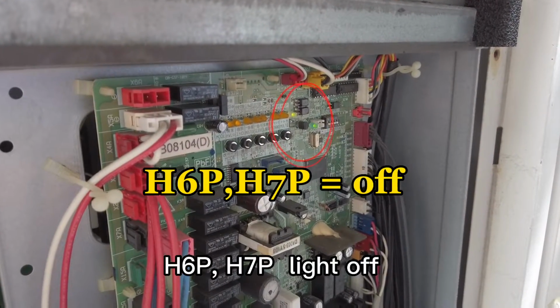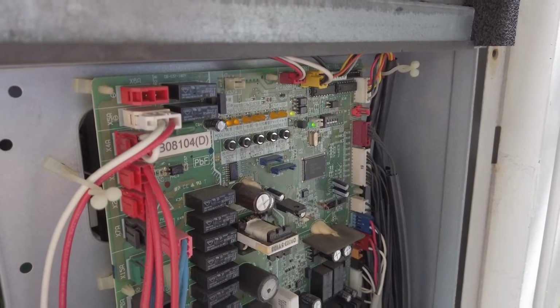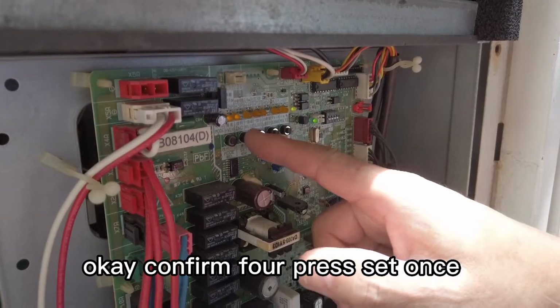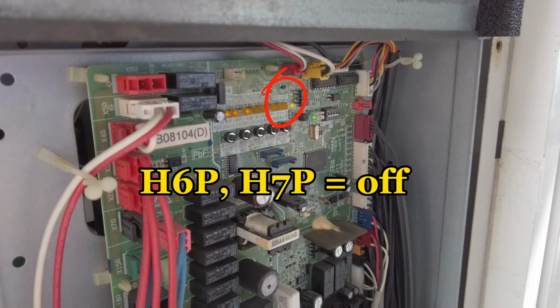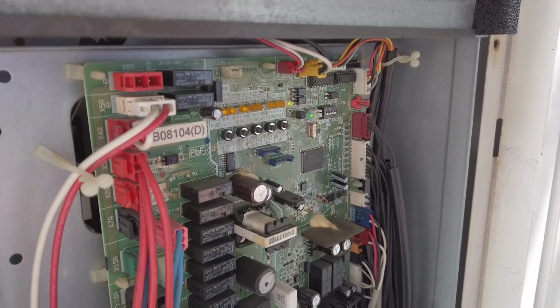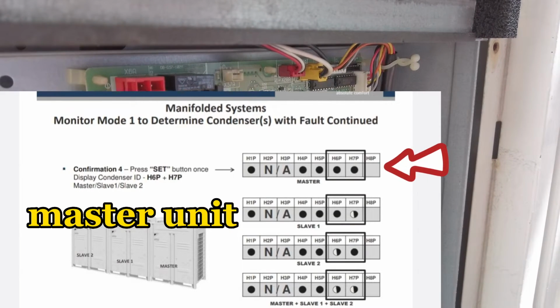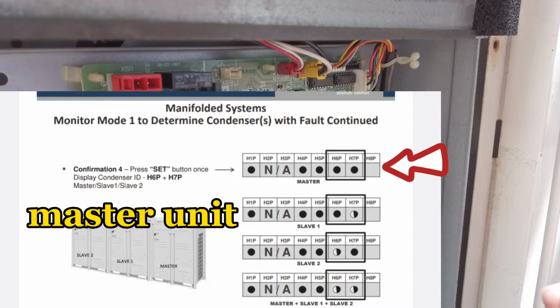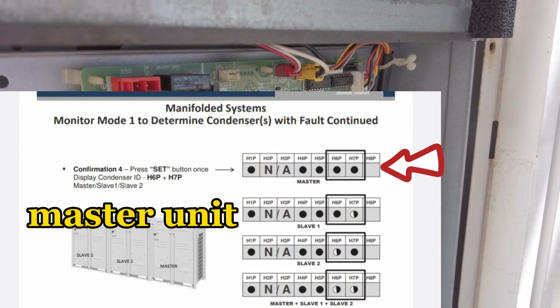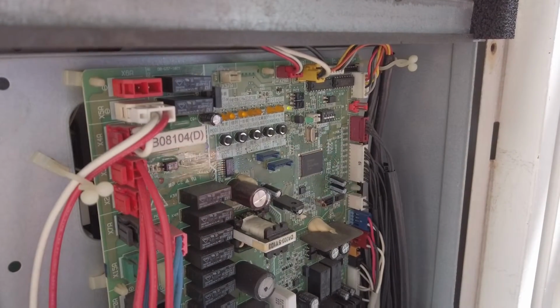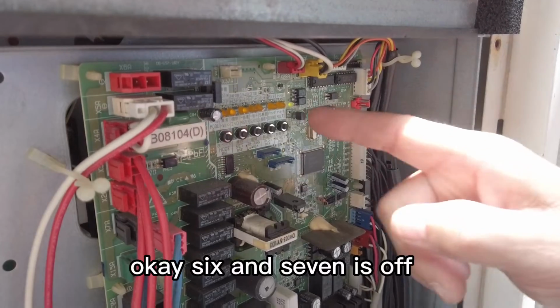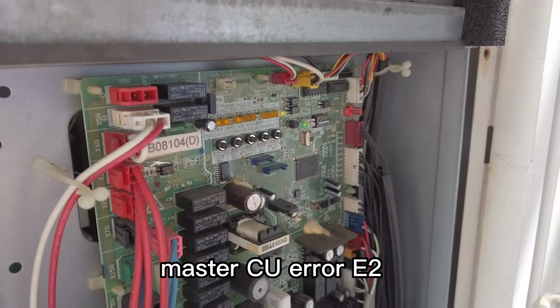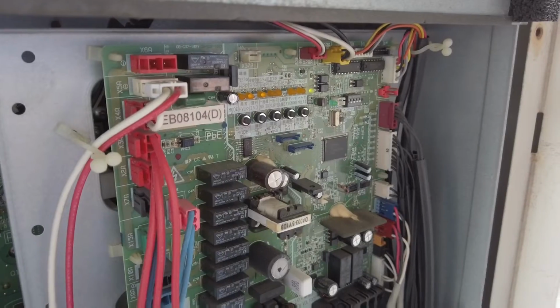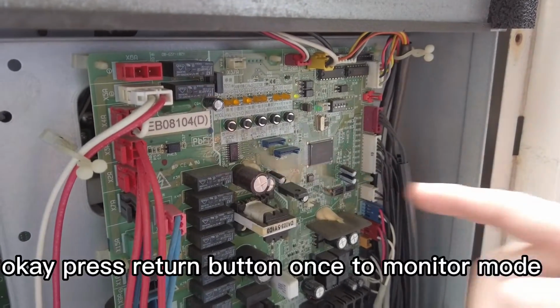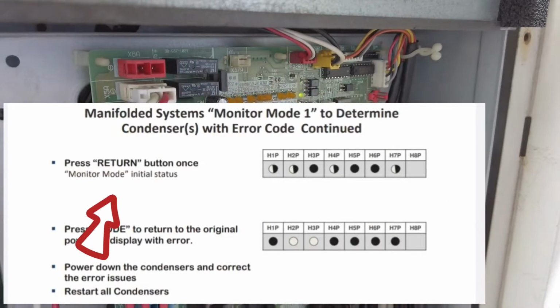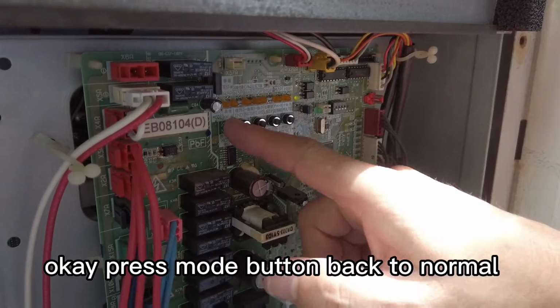Okay, confirm 3. Press set button once. Okay, LED 1 is blinking. LED 2 is on. Okay, confirm 4. Press set once. Okay, LED 1 blinking, LED 2, LED 3 is on. Okay, 6 and 7 is off. Okay, press return button once to monitor mode. Okay, press mode button back to normal.